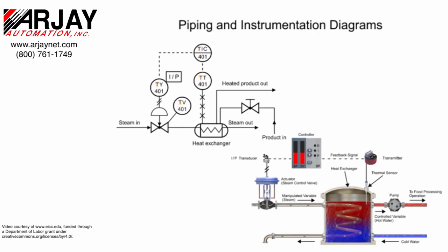The instrument connected to the heat exchanger contains two other types of information. The second letter in the functional identifier indicates it is a transmitter and the balloon with no line inside its symbol indicates the device is field mounted.